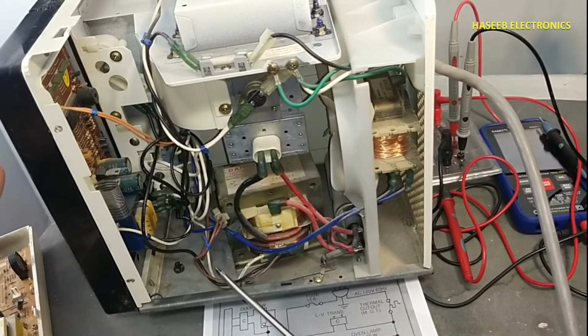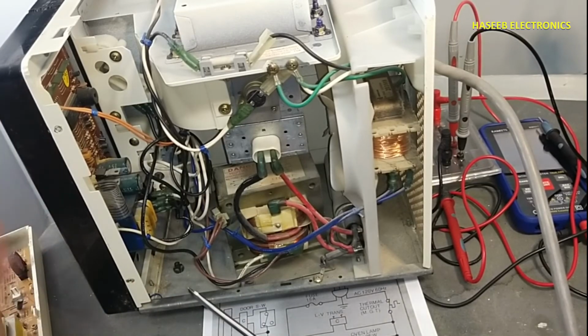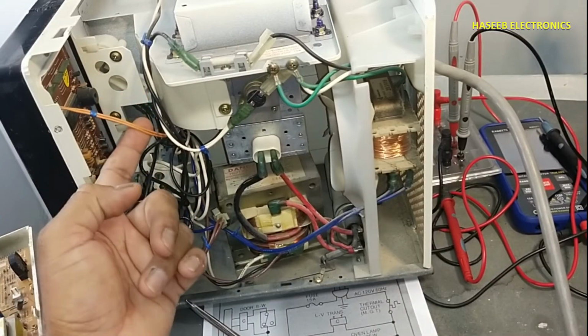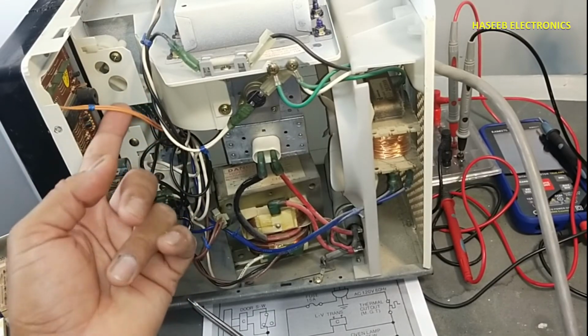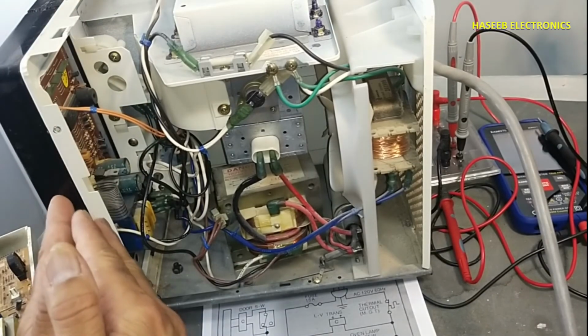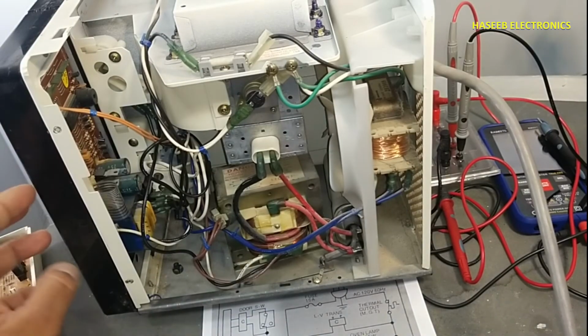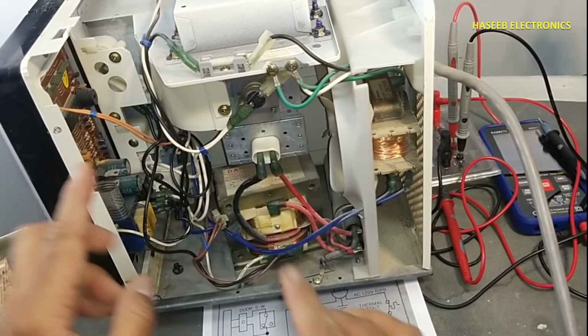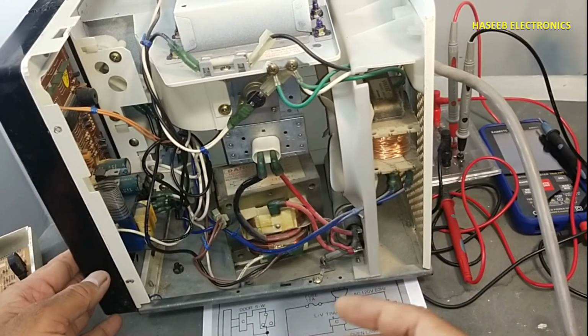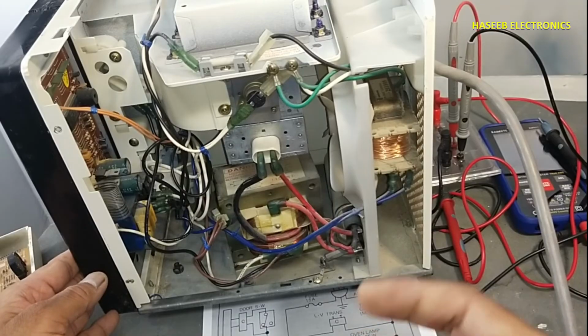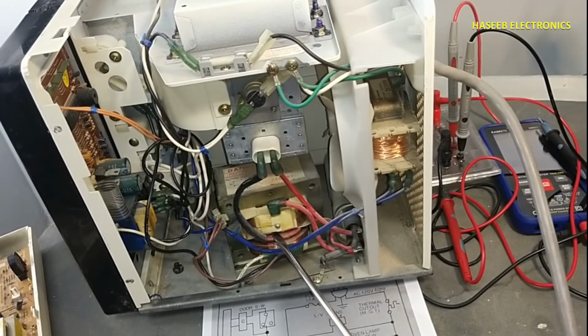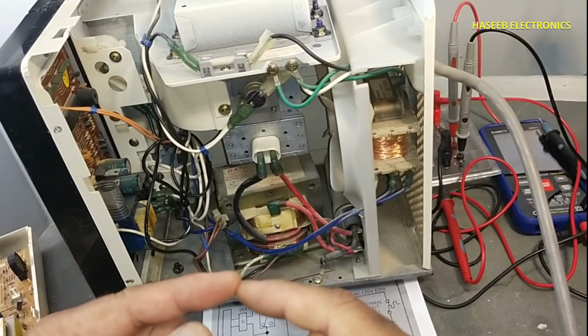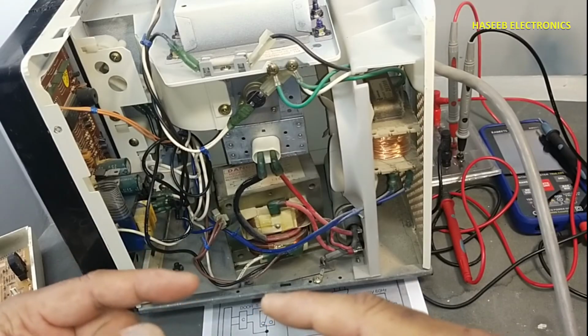The next fault: when we provide a program, the counter will not start. At that time this switch is not opening, and it must be open. In this Samsung brand, when the door is closed, it must be an open circuit. If this switch is not making open contacts, it will not start the counter, and in some conditions we feel sparks and heavy sound. Most of the time this power transformer, the high voltage transformer, makes sparking. When it makes sparking, it makes sparks and heavy sounds.